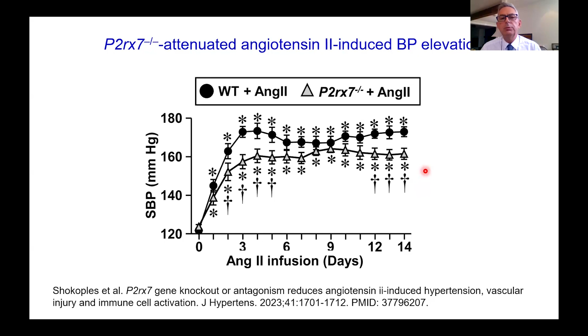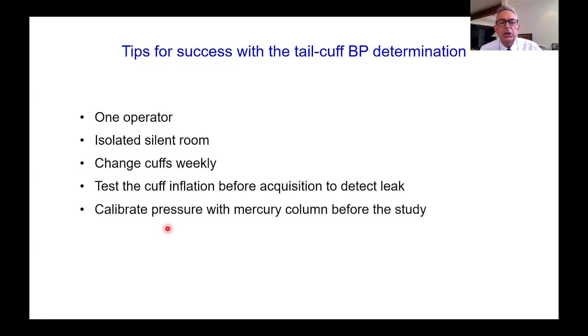Now we'll show you tips to get good tail-cuff blood pressure. It should be one operator. You should use an isolated silent room, change the cuff weekly, test the cuff inflation between acquisitions to detect leaks, and calibrate pressure with a mercury column before the study.